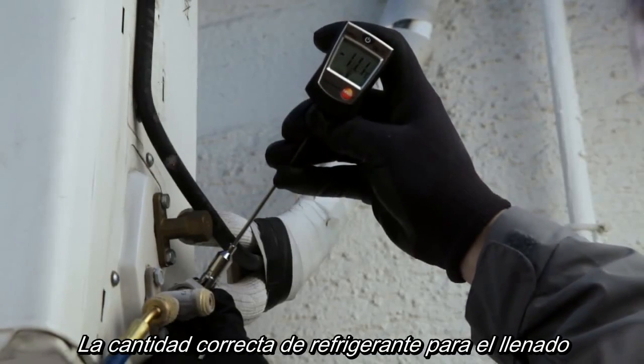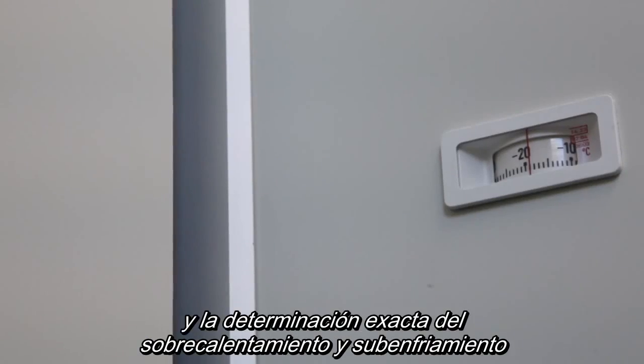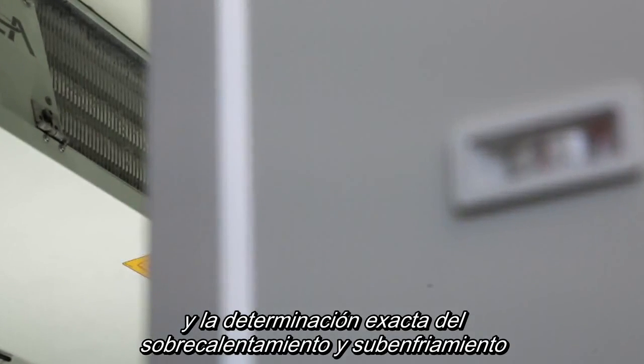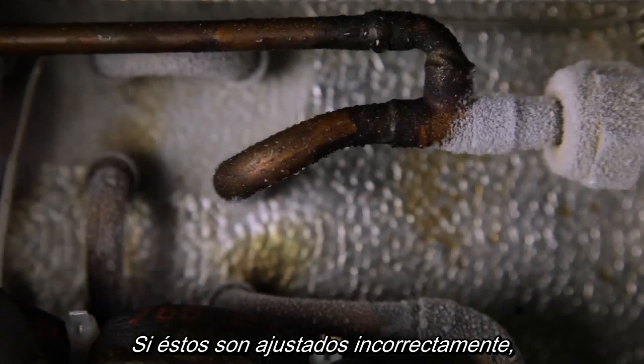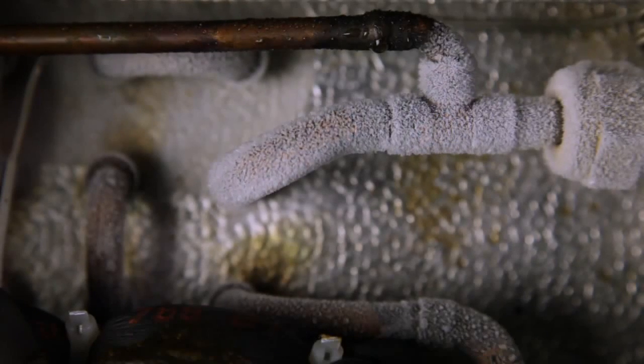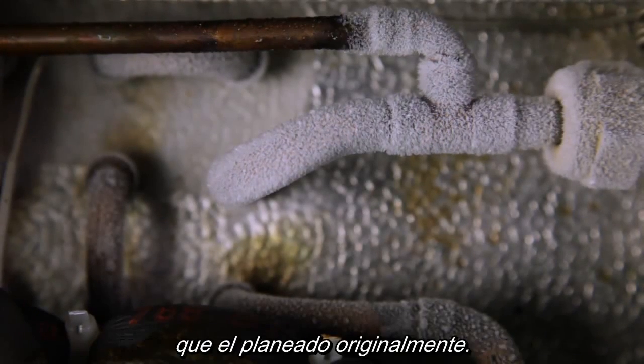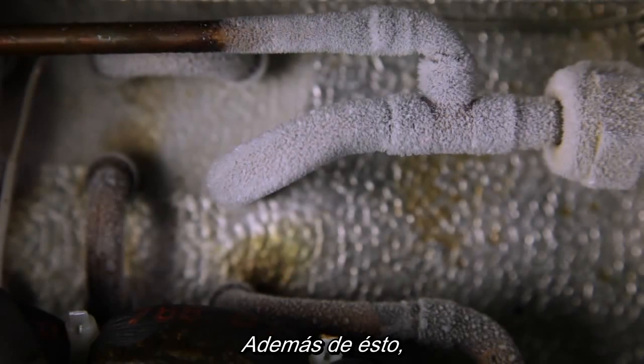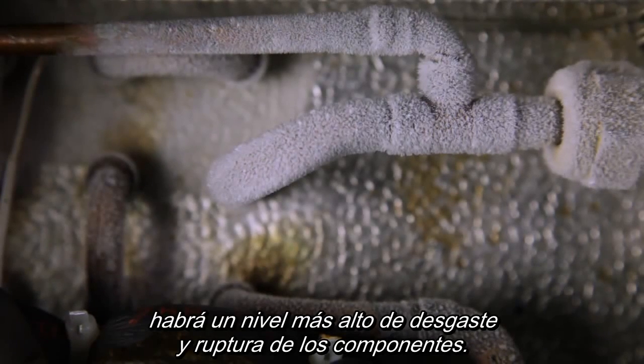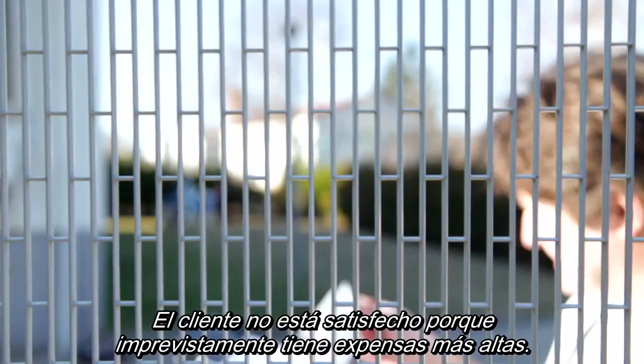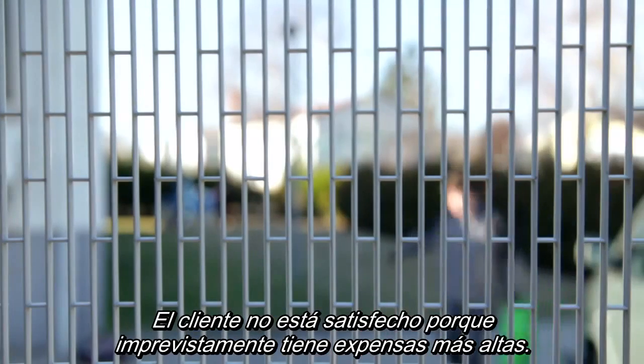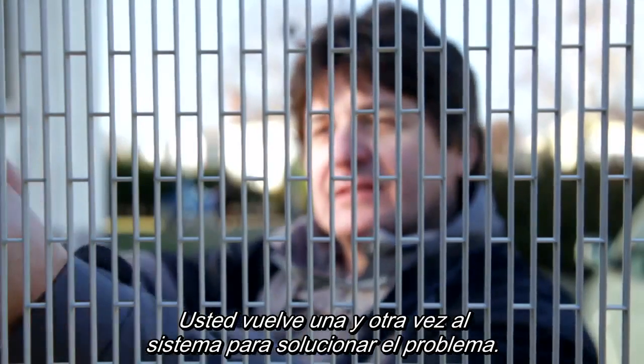The correct refrigerant filling quantity and the exact determination of superheating and subcooling are crucial parameters. If these are incorrectly adjusted, the system has higher energy costs and a lower refrigeration performance than originally intended. On top of this is a higher level of wear and tear on the components. The customer is dissatisfied because he has unforeseen higher expenses. You keep coming back to the system in order to solve the problem. This can even damage your reputation as an expert business.